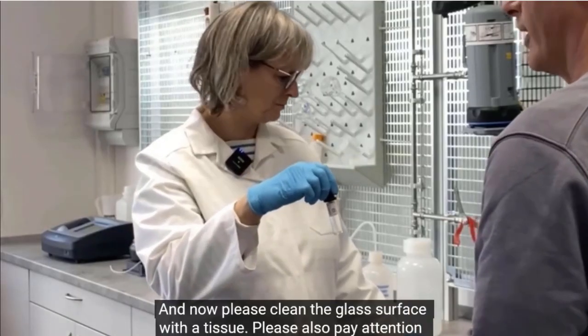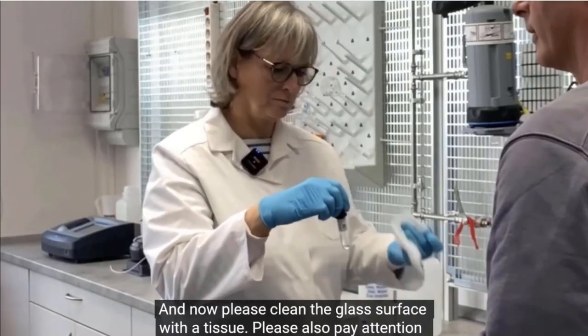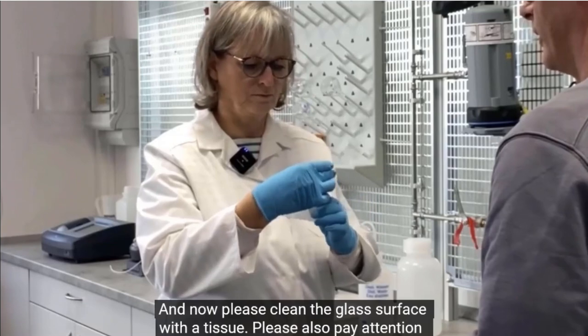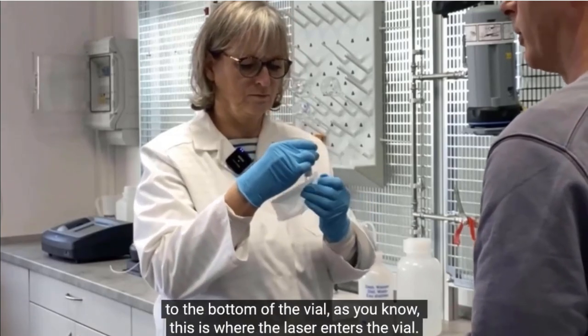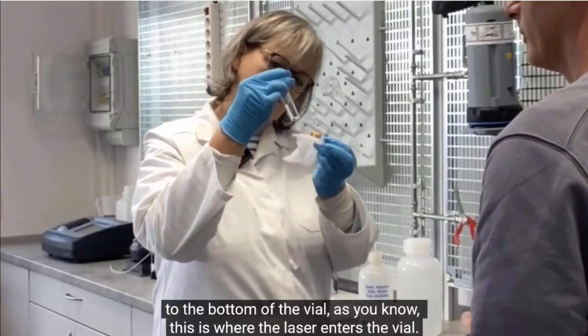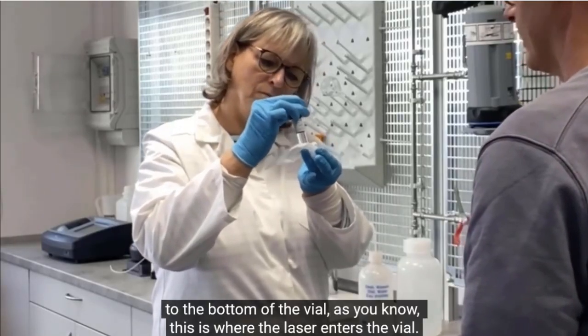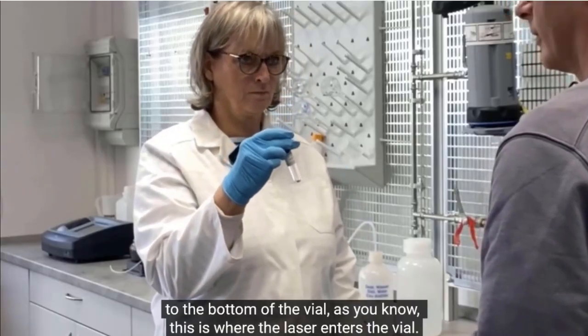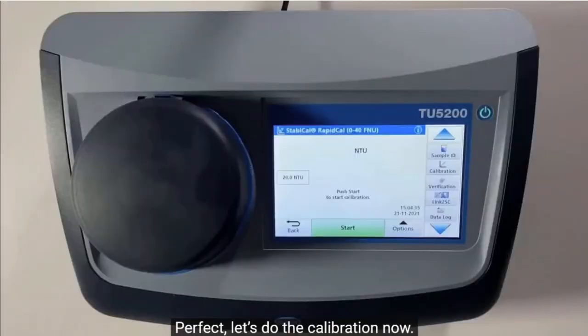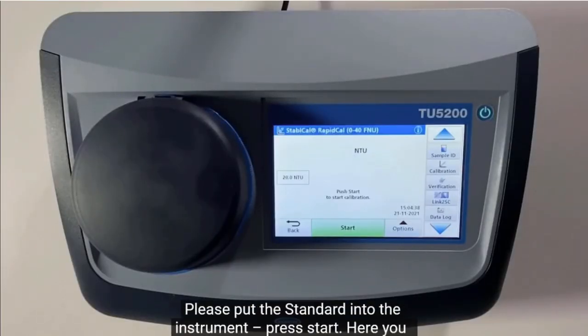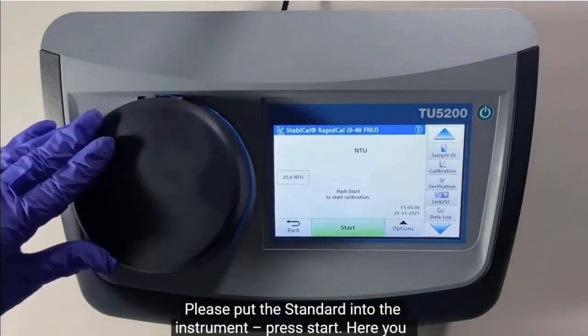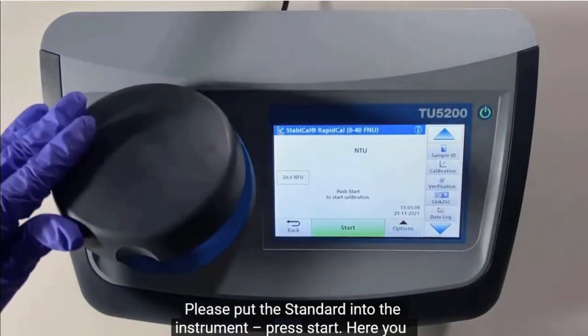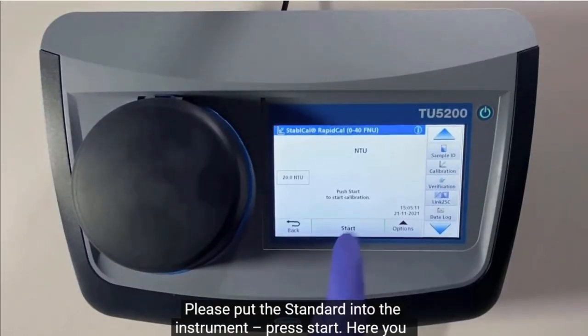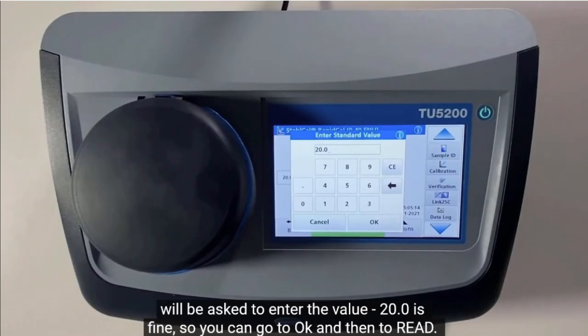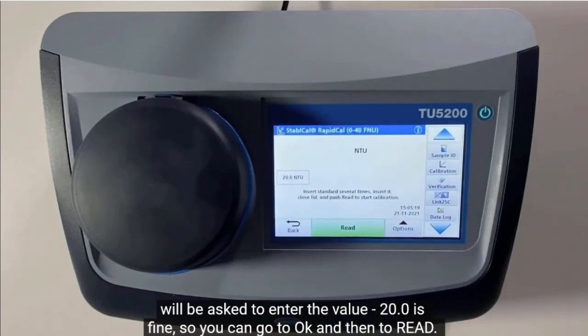And now please clean the glass surface with a tissue. Yeah, very good. Please pay attention also to the bottom of the vial. As you know, this is where the laser enters the vial. Perfect. Let's do the calibration now. Okay, please put the standard into the instrument. And now press start. So you will be asked to enter the value. 20.0 is fine. So you can go to OK and then to read.